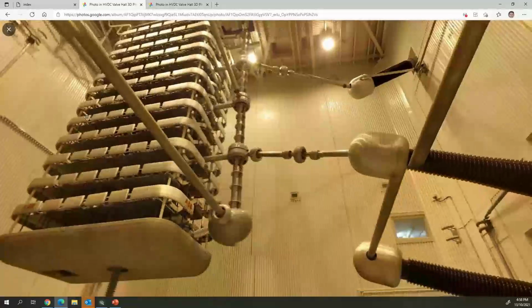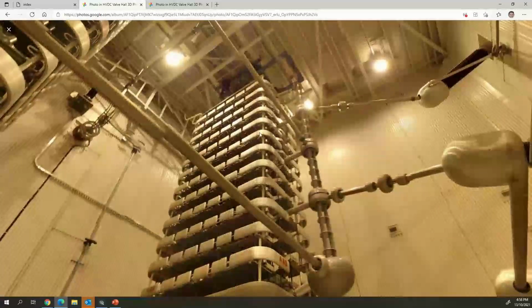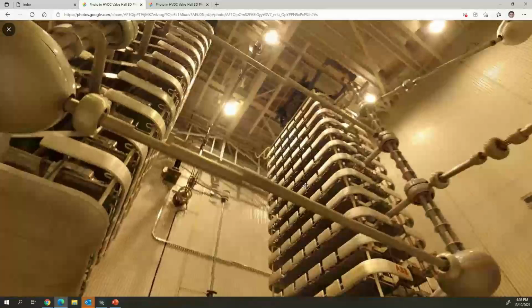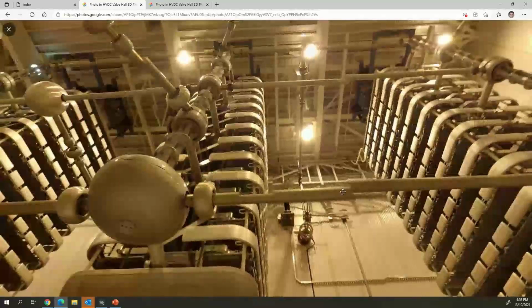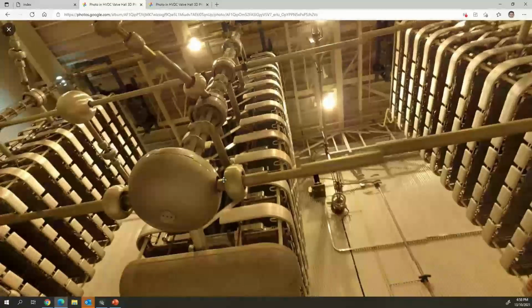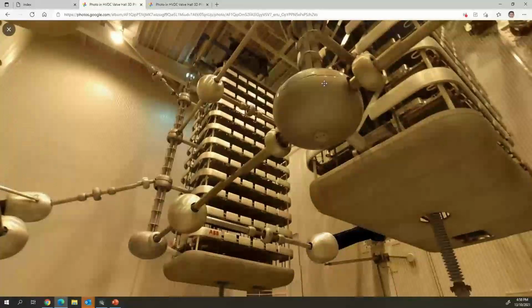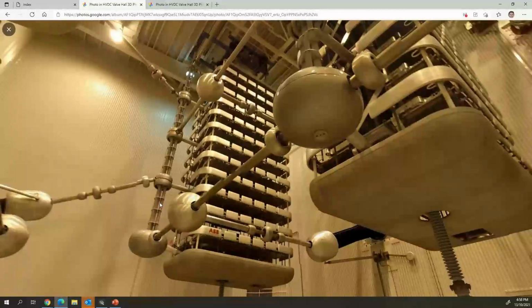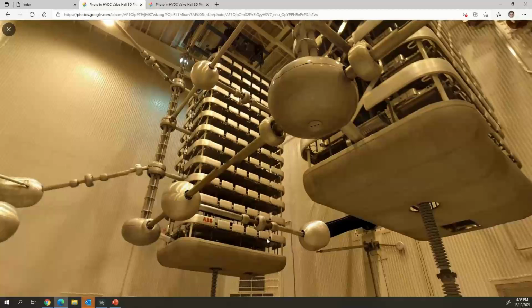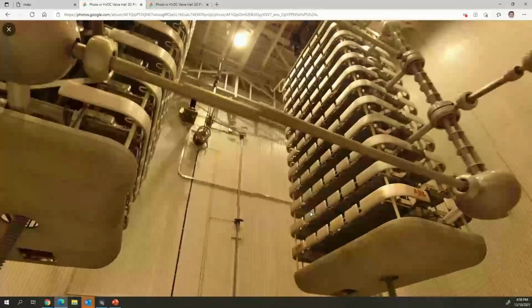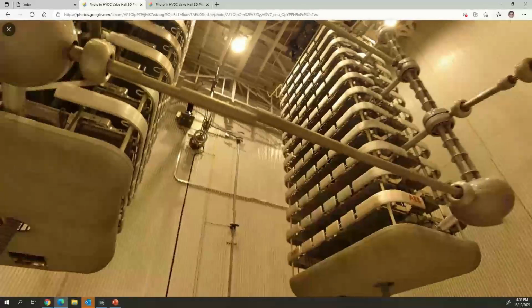So this is called a quadra valve. ABB call it a quadra valve. Siemens call it a quadruple valve. Same thing. You can also see these arrestors over each valve. It's to protect it during transients. And this is our DC coming out through this big bushing down the bottom here. So it's tapped off the bottom. This is our 350 kV DC. And the top is connected to the neutral connection. So that's going through this tiny little bushing up here. That's only, doesn't have to be rated for the full voltage.